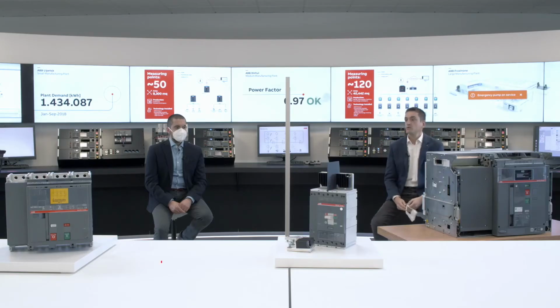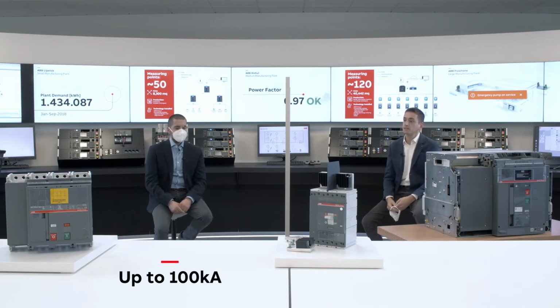Bye. Thank you. And now, let me introduce you to our colleagues Riccardo Breda and Nicola Perico, who are global product specialists for air and molded case circuit breakers. Good morning, guys. We are seeing that the capability to withstand the fault current is becoming more and more common in applications like battery energy storage systems. Can you kindly explain how we are approaching this requirement? Thanks, Marco. With ACBs today, we can reach up to 100 kA Icw for 1 second. With that goal in mind, we developed our new switch disconnector based on the Emax 2 air circuit breaker up to 1500 volts DC.